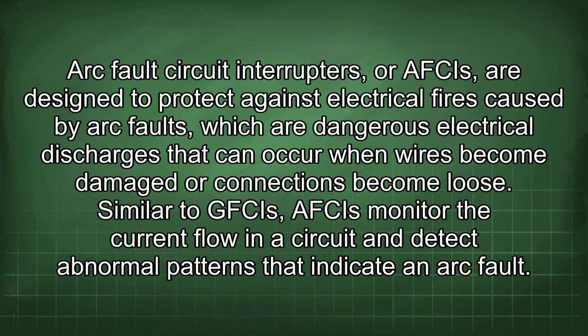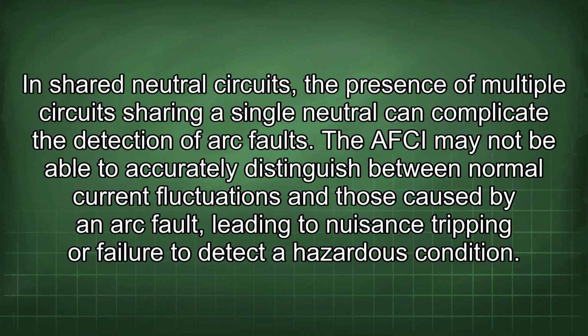Arc fault circuit interrupters, or AFCIs, are designed to protect against electrical fires caused by arc faults, which are dangerous electrical discharges that can occur when wires become damaged or connections become loose. Similar to GFCIs, AFCIs monitor the current flow in a circuit and detect abnormal patterns that indicate an arc fault. In shared neutral circuits, the presence of multiple circuits sharing a single neutral can complicate the detection of arc faults. The AFCI may not be able to accurately distinguish between normal current fluctuations and those caused by an arc fault, leading to nuisance tripping or failure to detect a hazardous condition.